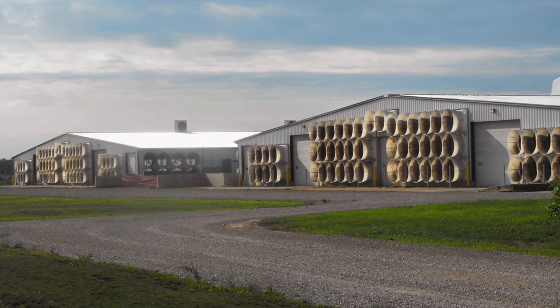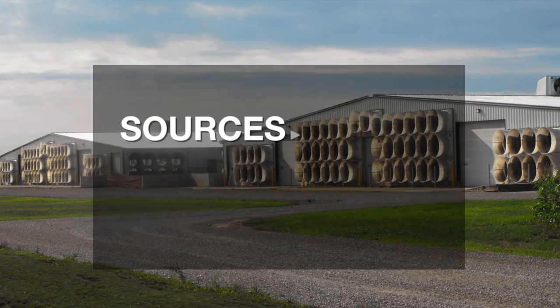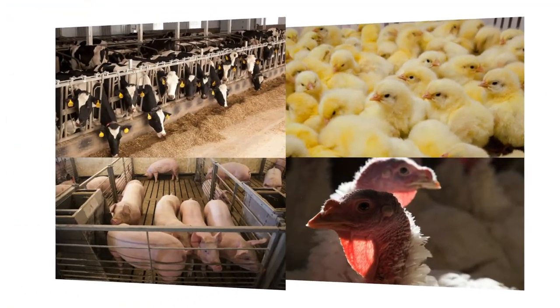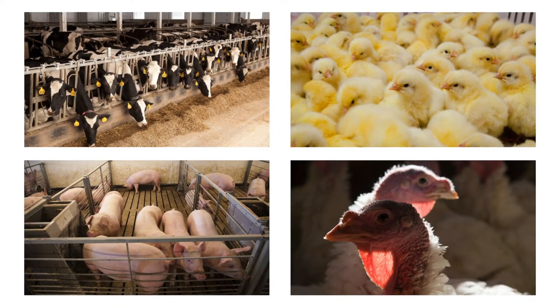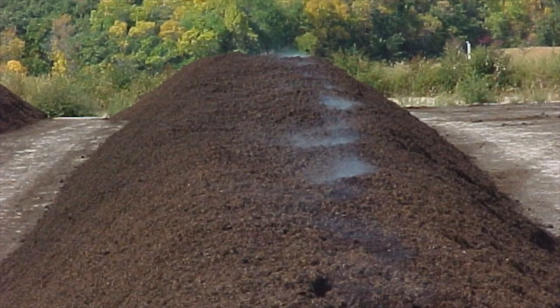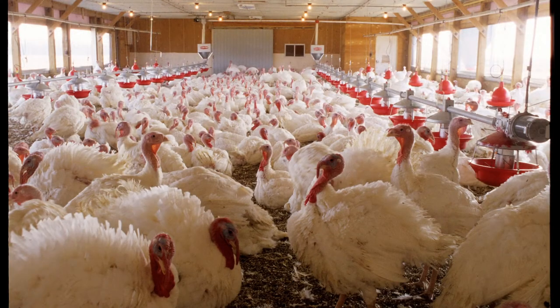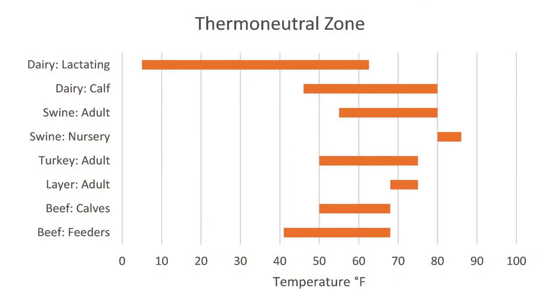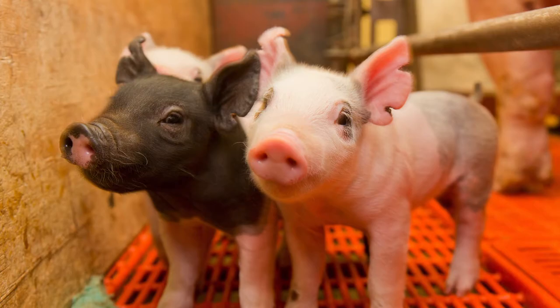A well-designed ventilation system takes into account the sources of the heat, moisture, and gas generated in the barn. These sources are a function of the type, number, and size of animals in the building, as well as the type of manure handling system. Other things to consider are heat or cold coming from non-insulated walls or ceilings. The system should also take into account the thermoneutral zone of the animals in the barn. Thermoneutral temperatures vary greatly among livestock species, and they also vary with the animals' age.